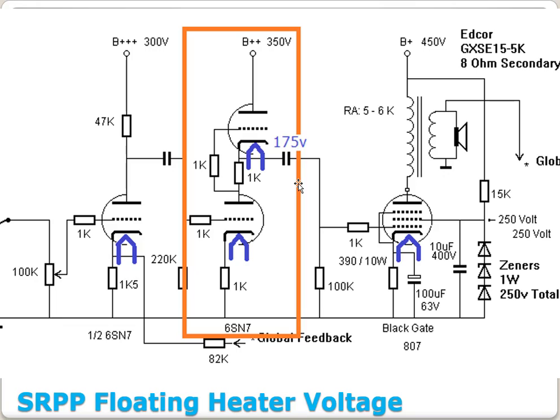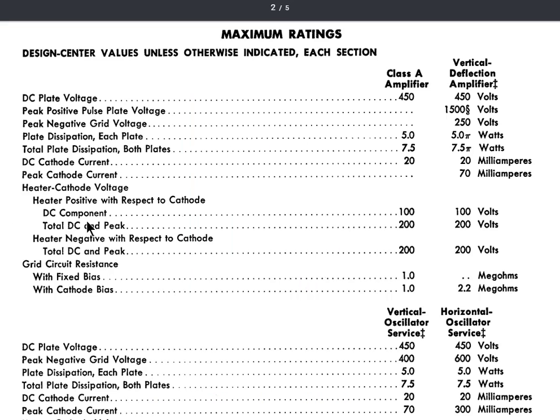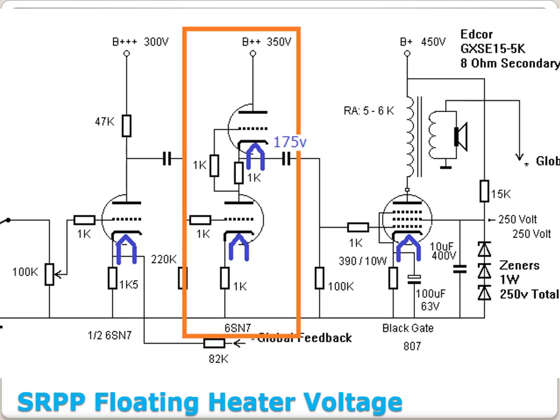So the way you get around that delta between these two is you float the heater voltage on this one. And remember, the original design only floated the heater voltage on this tube. But what I mentioned was it wouldn't hurt to float the heater voltage on all of these tubes up to the 80 volt point. So even though we've got these cathodes closer to ground, they're not outside of that 200 volt specification going the other way, the reverse polarity either. So we're in good shape. I just wanted you to understand the reason we're floating those heaters.